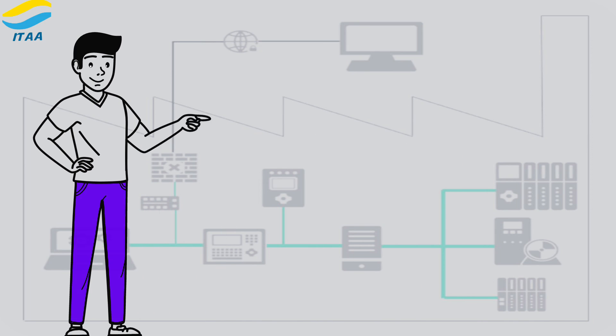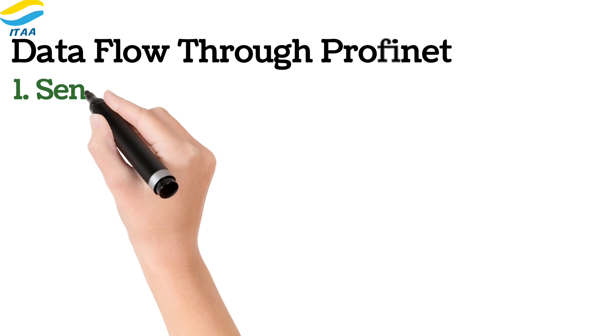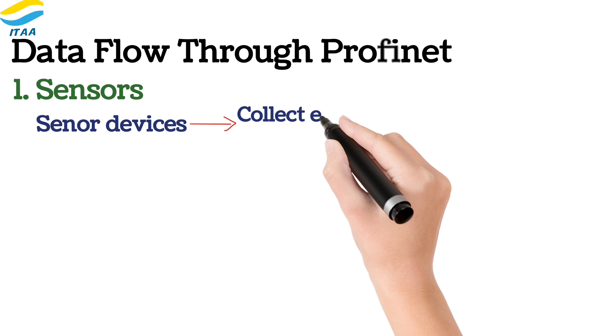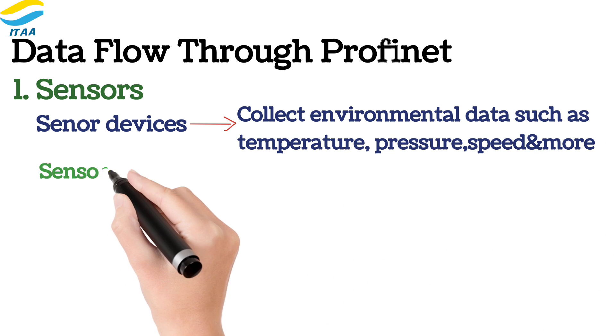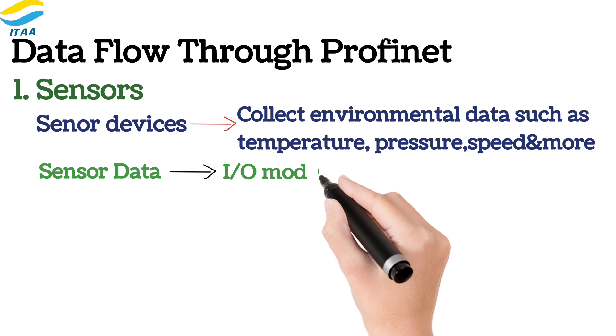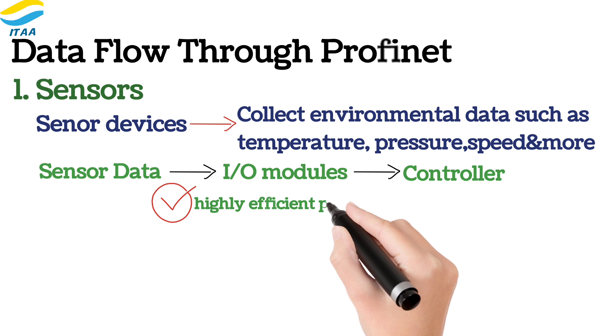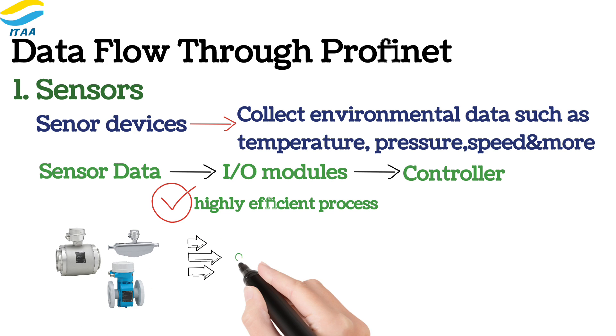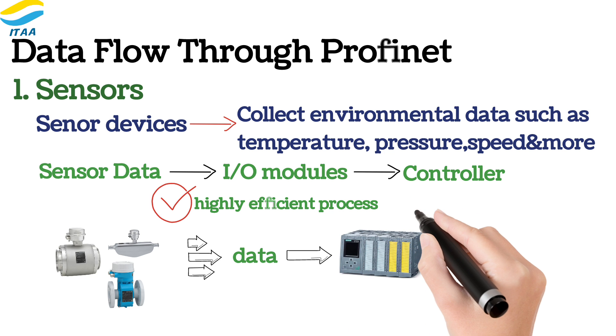Now let's talk about how data flows through a PROFINET system. The first type of data flow begins with the sensors. These devices continuously collect environmental data such as temperature, pressure, speed, and more. The sensor data is sent to I/O modules, which then forward the data to the controller. This is a highly efficient process with data being exchanged in real-time, often in cycles as short as a few milliseconds. Sensors detect changes in real-time, feeding this data to the controller so that it can make decisions quickly.